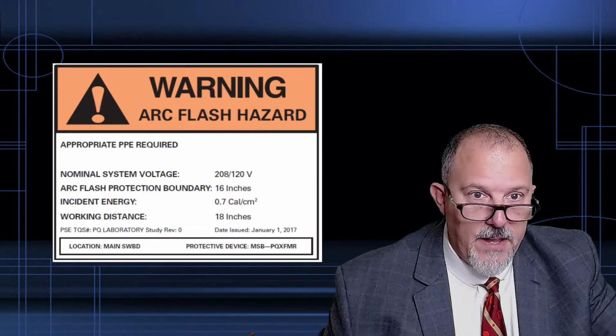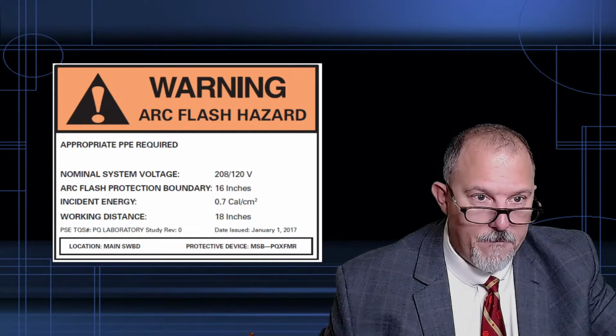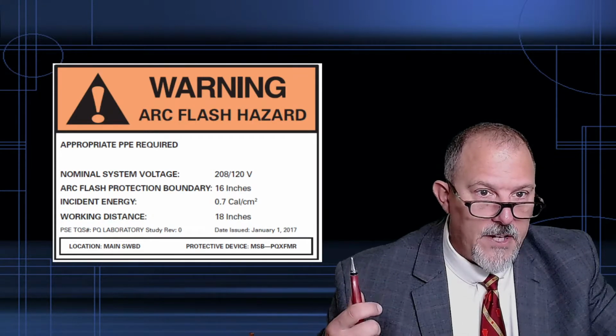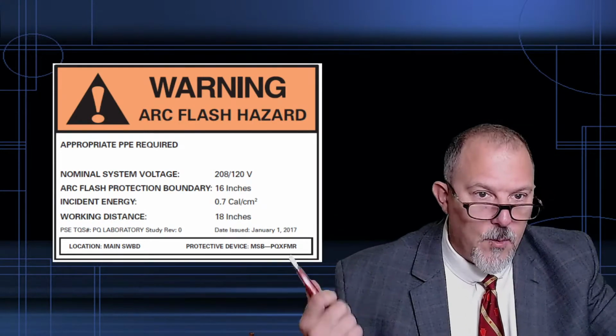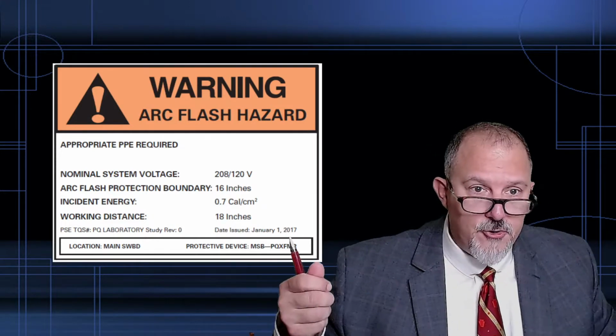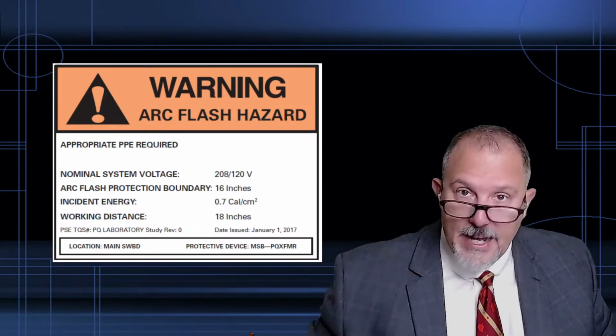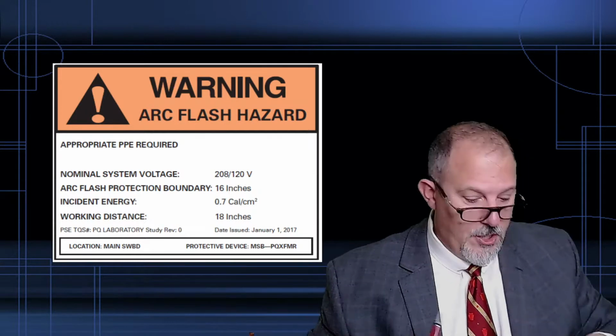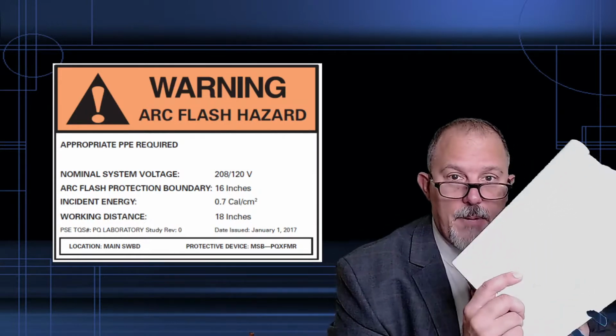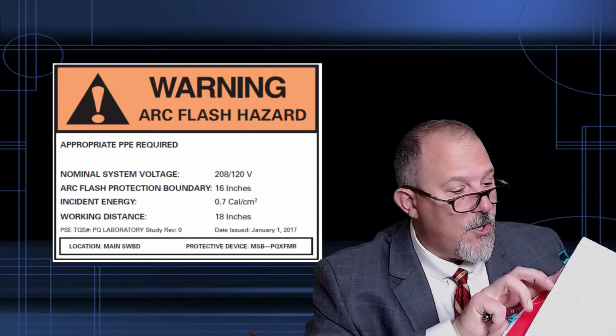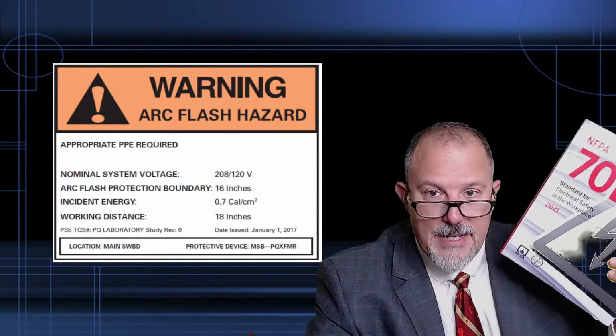And I also have to have my arc flash boundary, which this arc flash protection boundary is 16 inches, and my working distance. So I have my arc flash boundary, I have my incident energy, and I have my working distance, and I have my voltage. That is what's required by this. The date is not required by 70E.